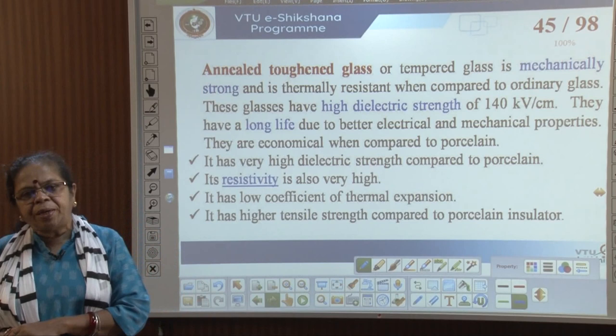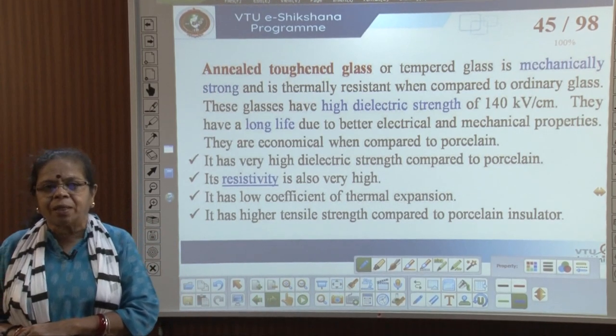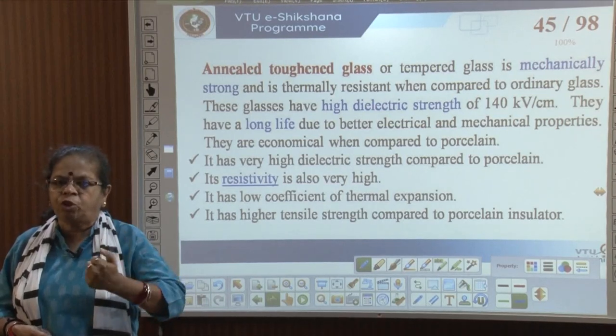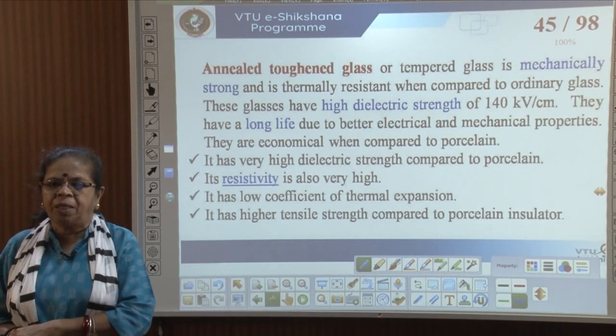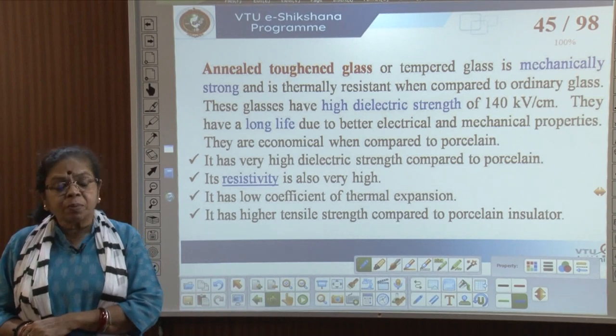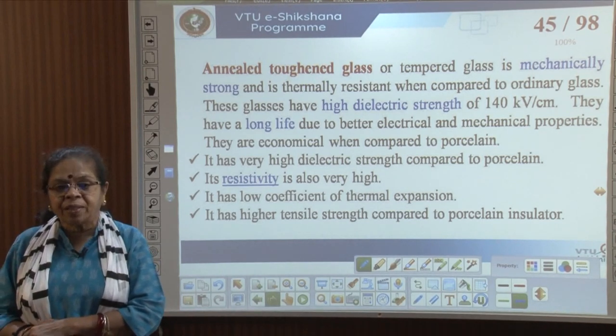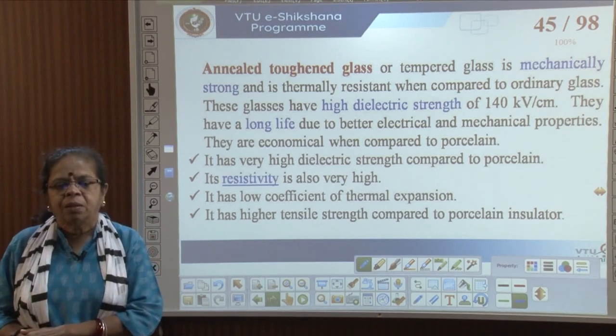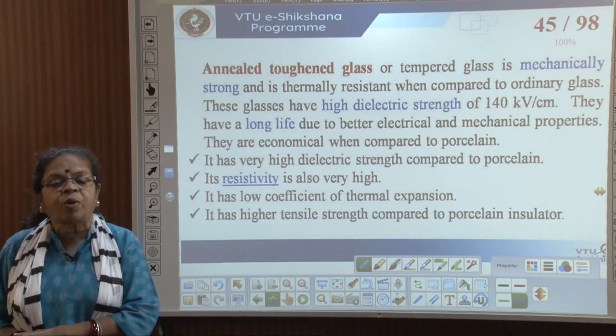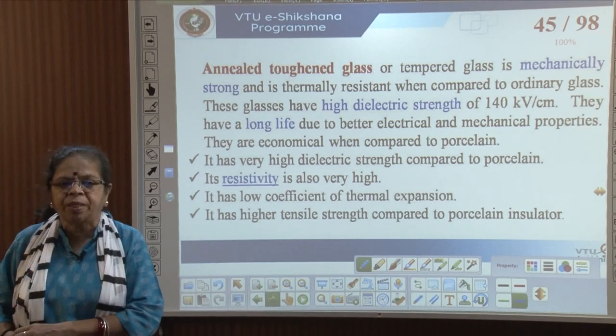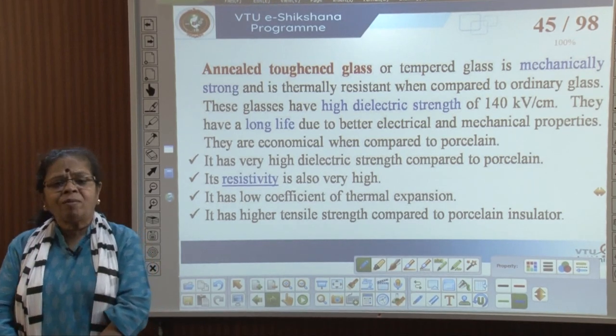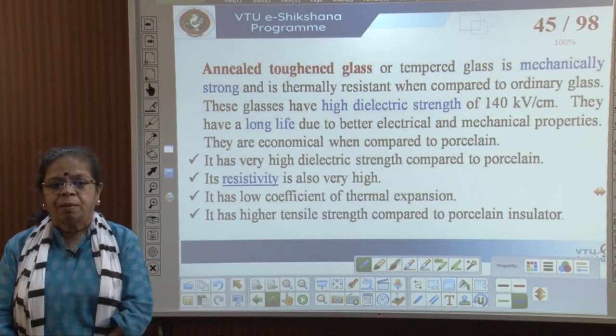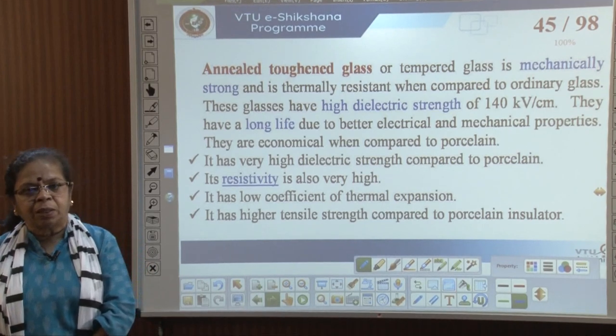The other commonly used material is glass — annealed and toughened glass. Annealing is a controlled temperature variation process to strengthen materials. Toughened glass is mechanically very strong and thermally resistant compared to common glass. It has a very high dielectric strength of around 140 kV/cm, long life due to better electrical and mechanical properties, and is cheaper than porcelain.